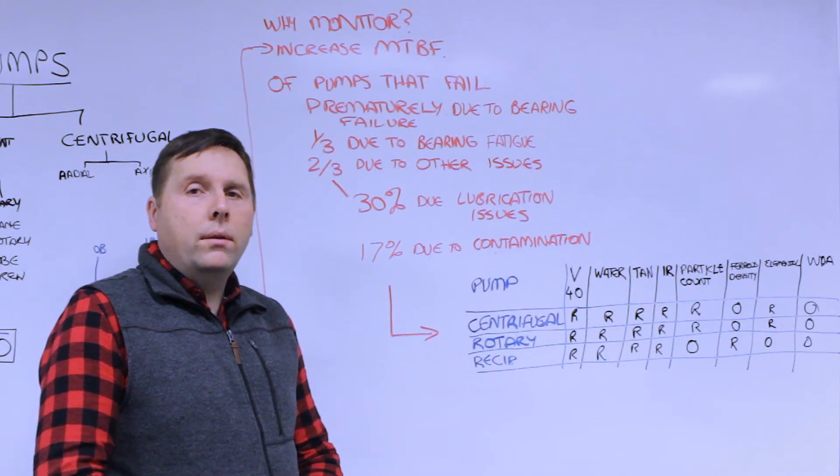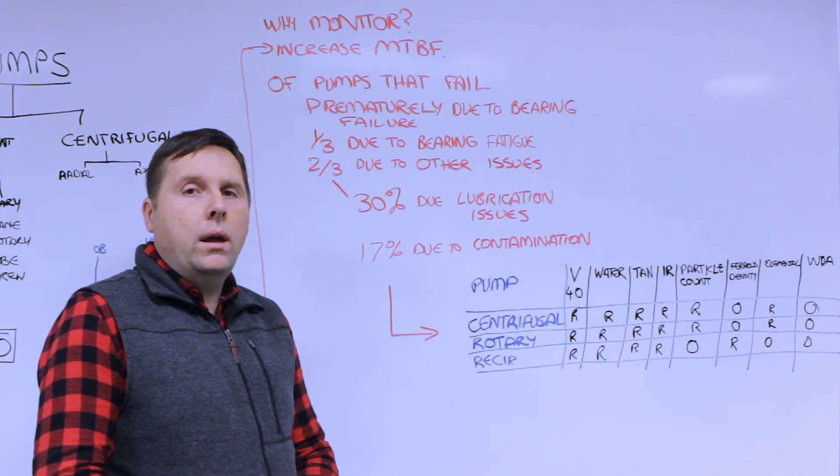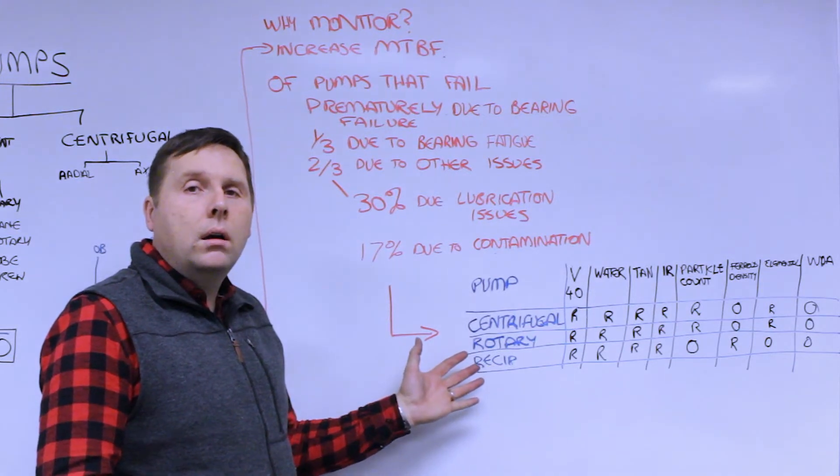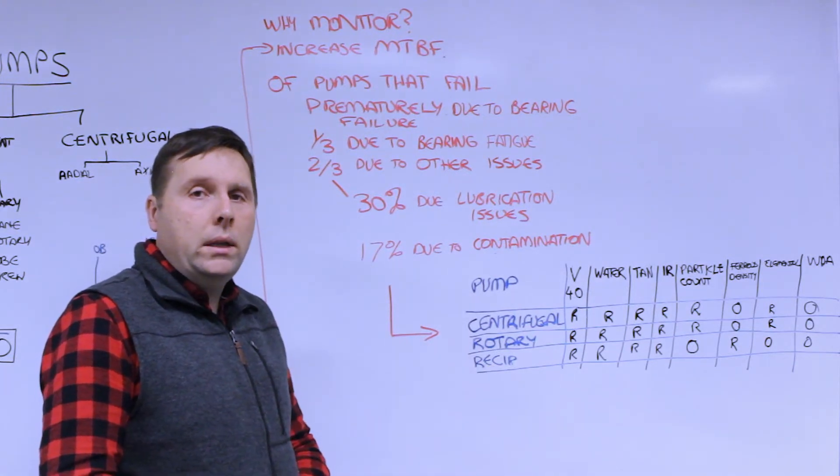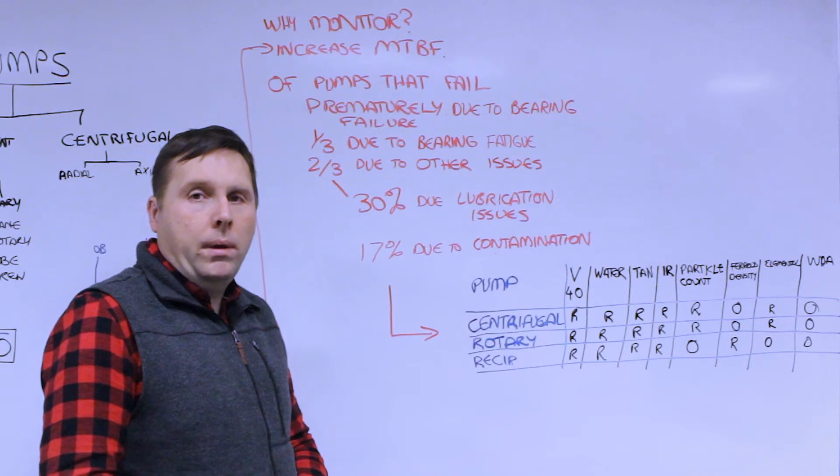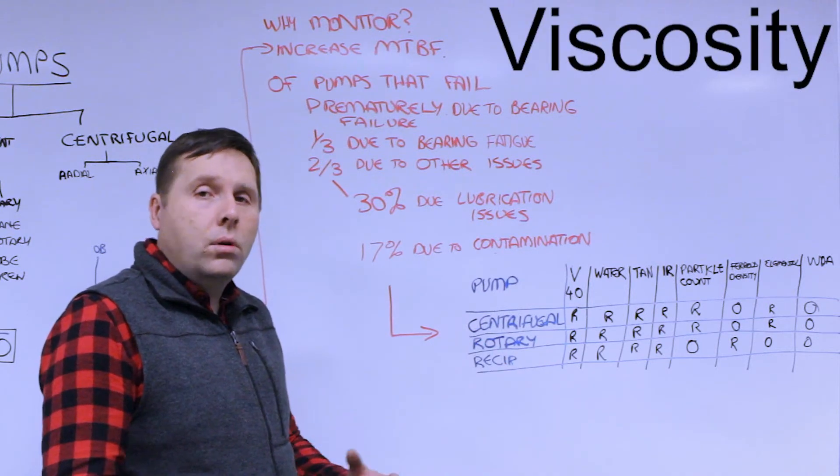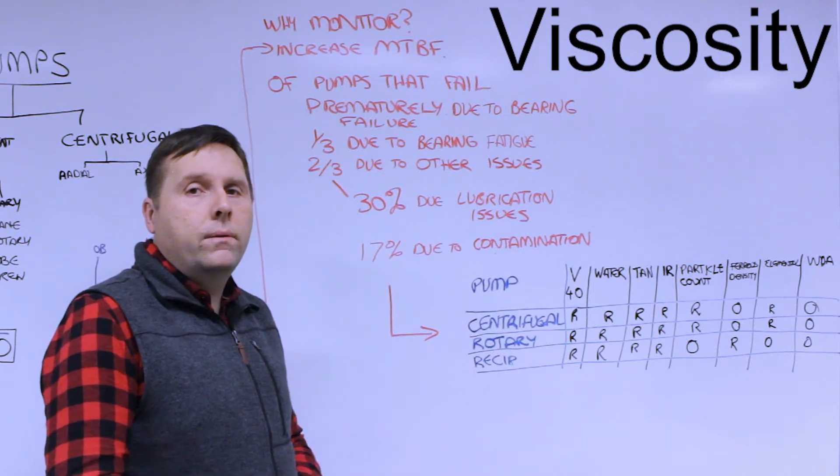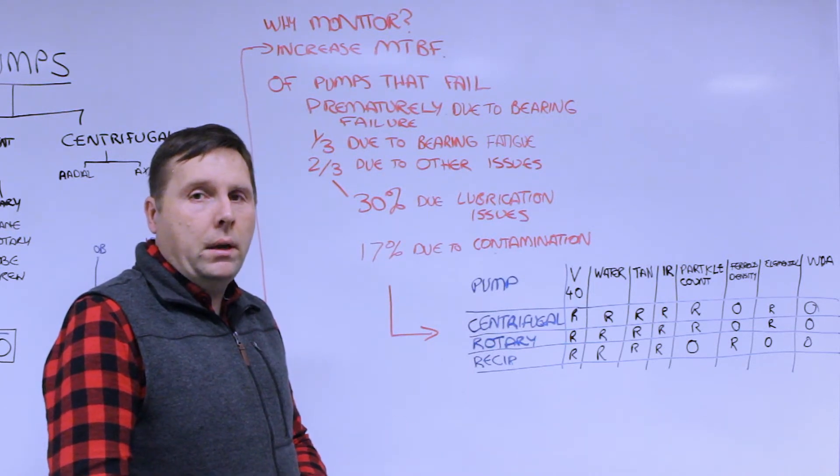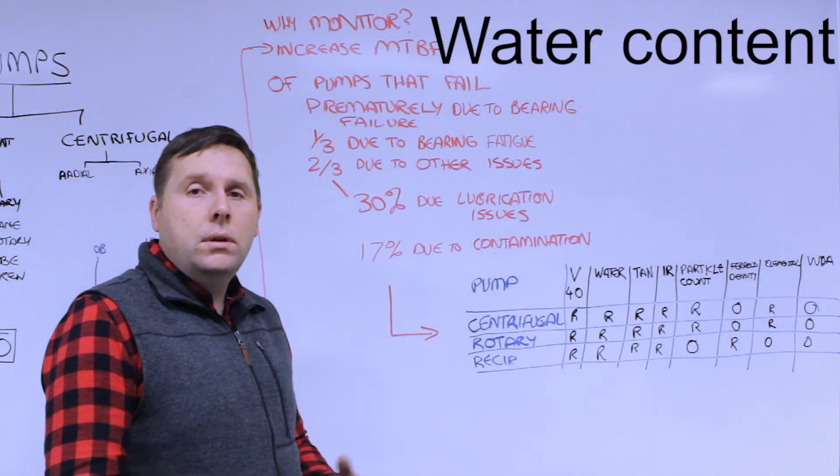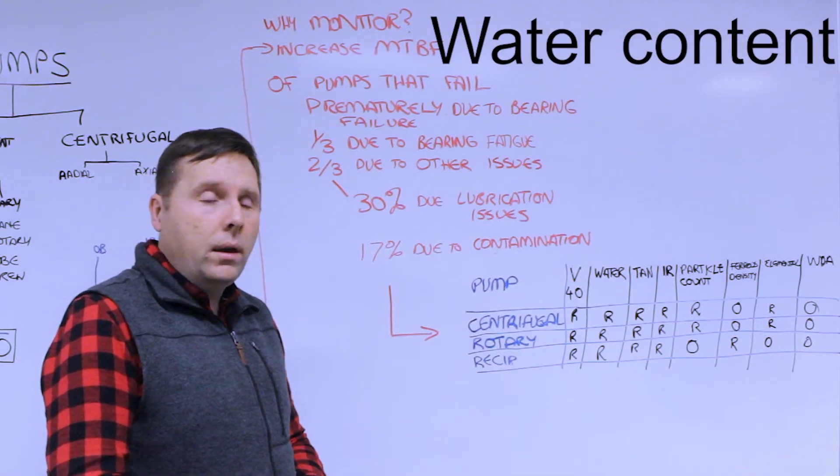With pump oil analysis, what are the tests that we care about? Here's an overview of what is most commonly checked for pump applications. We want to check viscosity - it's the most important physical property and critical for any lubrication of a pump bearing as well as the pump impellers. Water content to indicate if there's any contamination due to water.